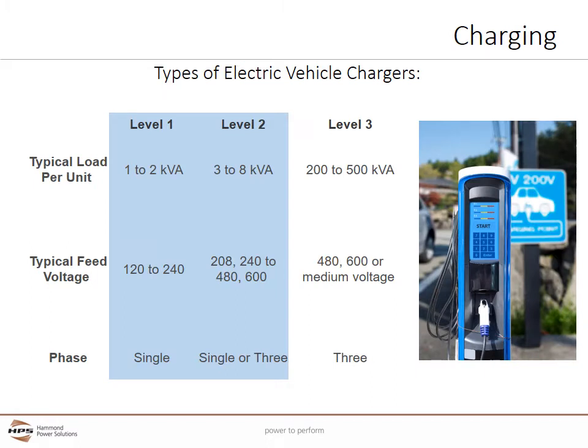In order to understand the demand of a transformer, we need to understand the demand from the chargers. Level 1 and Level 2 chargers are the lowest cost and most common chargers. Both use the vehicle's onboard charger to do the actual DC rectification. Level 1 and 2 chargers are single phase, typically provide 2 to 11 miles of range per hour, have a low installation cost, and usually need between 1 and 8 kVA of load per charging point. Three-phase transformers often need to be specified when large numbers of these chargers are installed, typically in parking lots and for fleet vehicles. Large numbers of charging points may be fed from a medium voltage source, and as we discussed earlier, can cause significant power quality problems.